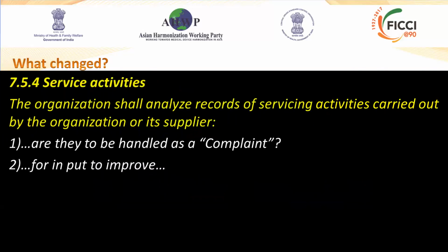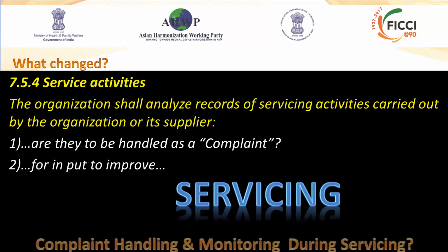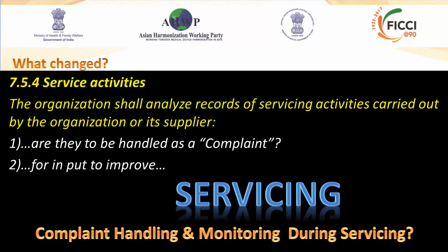Servicing activities. The organization shall analyze records of servicing activities carried out by the organization or its suppliers. And there needs to be much more attention under the 13485 standard where servicing personnel are concerned, because they are part of the complaint handling process. So making sure your servicing personnel are trained to handle complaints and report them to the complaint handling personnel within the organization is critical for the new 13485 standard.